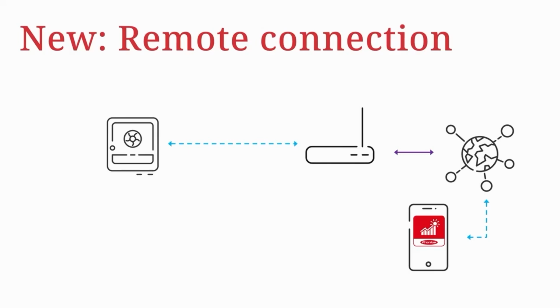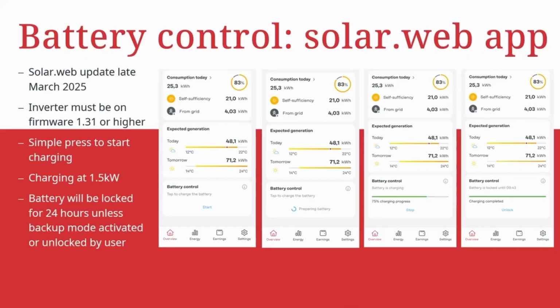The simplest solution is using the new battery control feature from within the Solar.web app. This will be released during March, so keep an eye out for software updates available for your Fronius Solar.web app. And what you'll be able to do is at the bottom of the screen, start a battery control charging session. This will slowly charge the battery at 1.5 kilowatts until it is fully charged. The battery will then hold its charge for 24 hours. This energy is only then discharged if there is a grid failure, or alternatively if you decide to unlock the battery and allow it to discharge back to the property.